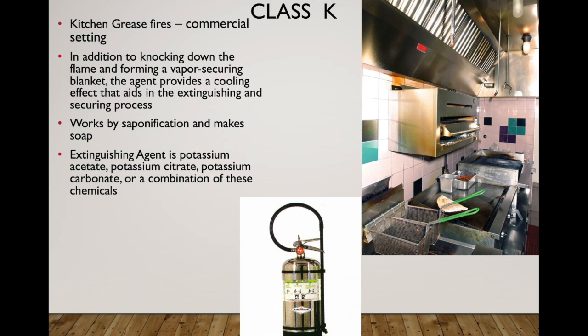And this led to some serious fire losses as a result, and they had to come up with this Class K chemical. So what this does, in addition to knocking down the flame and forming a vapor securing blanket, the agent itself, as you can imagine, actually cools and aids in the extinguishing process. So it works by a process called saponification, where it actually reacts and makes soap. This is actually also very important because dry chemical powder, as you can imagine, when you discharge it, it basically goes anywhere and everywhere and takes a very long time to actually clean it up afterwards.